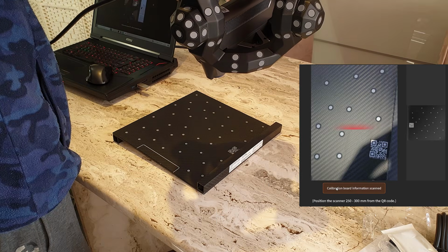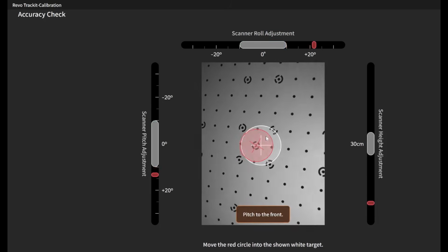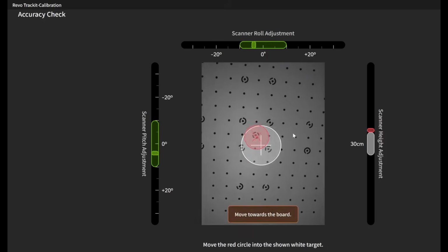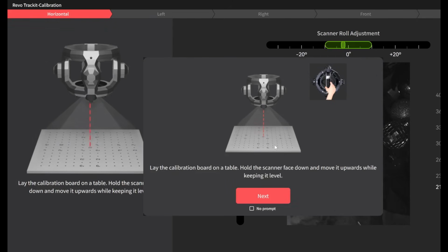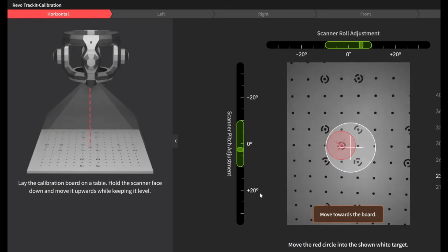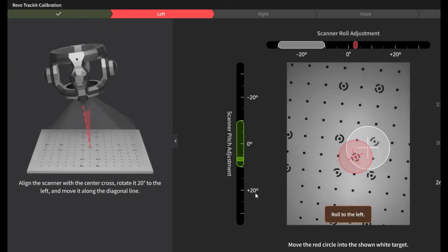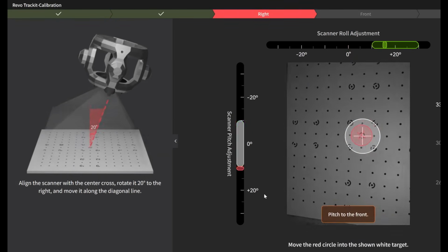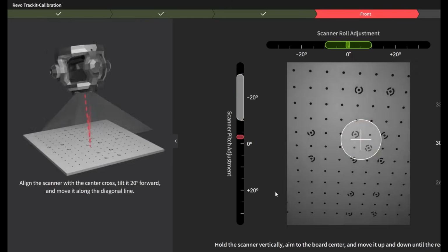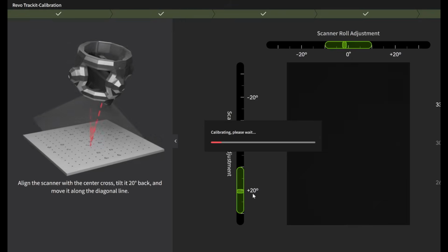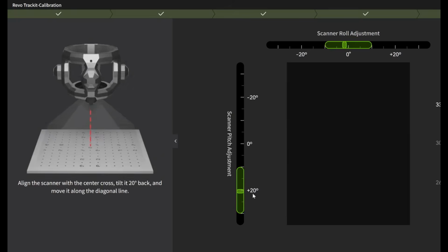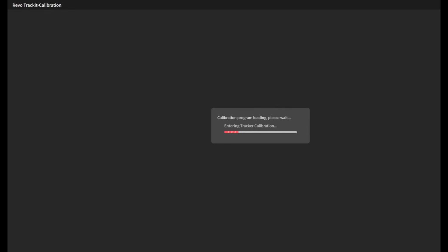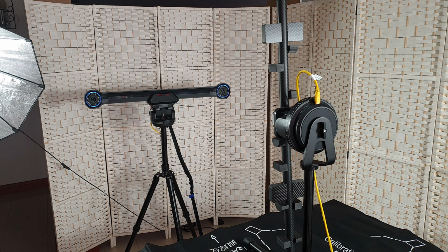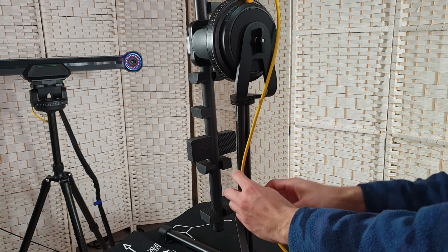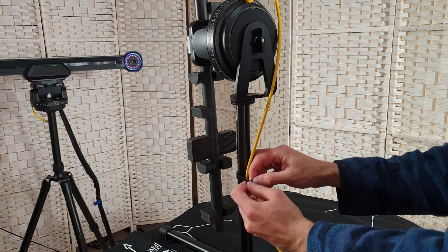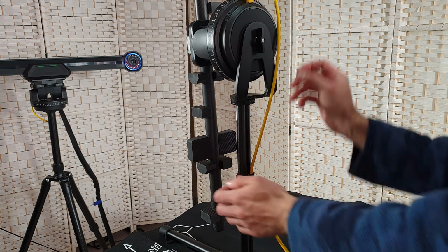First, we need to scan the 2 QR codes found on the calibration bar as well as on the calibration board, after which there are 3 stages of calibration, each with their own prompts to let you know what to do. However, I found if you disconnect during the calibration stage and you're, for example, on stage 2 out of 3, you cannot continue to stage 3 without having to restart the entire calibration. I think they should add an option that lets you choose exactly which calibration you would like to perform, because if you successfully complete 2 out of 3 steps, there is no point in repeating the 2 steps which you've already done. So maybe a menu which lets you select which calibration steps you would like to perform.